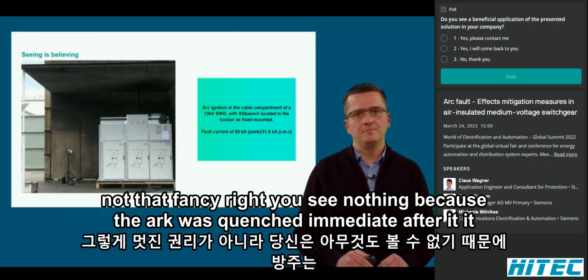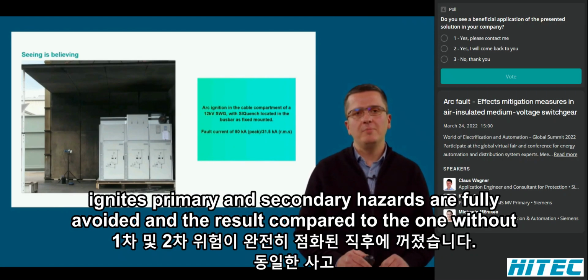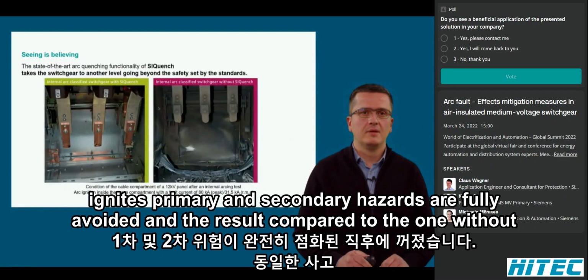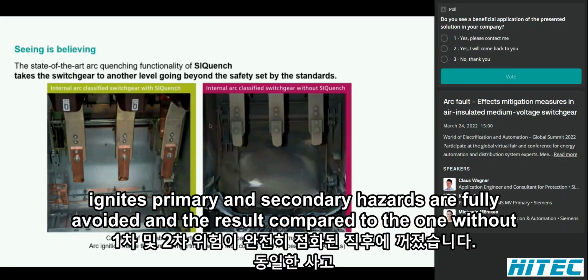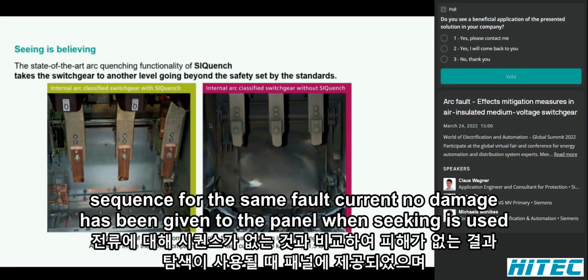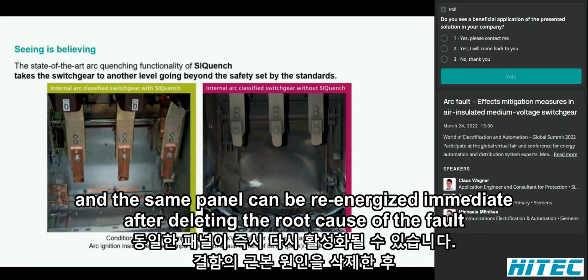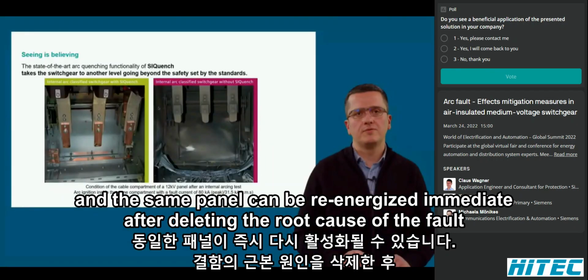Not that fancy, right? You see nothing, because the arc was quenched immediately after it ignites. Primary and secondary hazards are fully avoided. And the result, compared to the one without SiQuench for the same fault current. No damage has been given to the panel when SiQuench is used, and the same panel can be re-energized immediately after deleting the root cause of the fault.